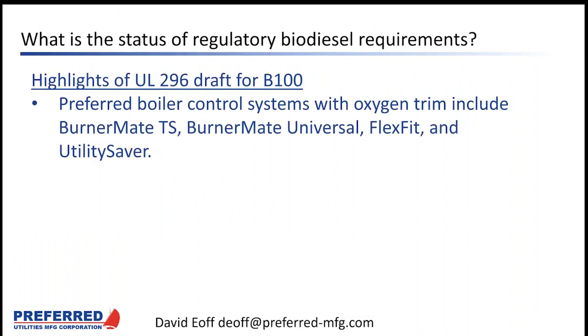Preferred offers a bunch of different control systems with oxygen trim that can automatically compensate for the different BTU content of biodiesel versus regular fossil diesel, including our BurnerMate TS, our BurnerMate Universal, our newer FlexFit controller, and our really older Utility Saver. These systems work by including an oxygen analyzer in the stack that compares current oxygen levels to the set point oxygen levels determined the last time the boiler was tuned up. And then it adds or subtracts air to get the stack oxygen back to the set point. Now that UL has updated 296 to include B100, I expect we're going to see a lot more government agencies ramp up their plans to require facilities to burn biodiesel.